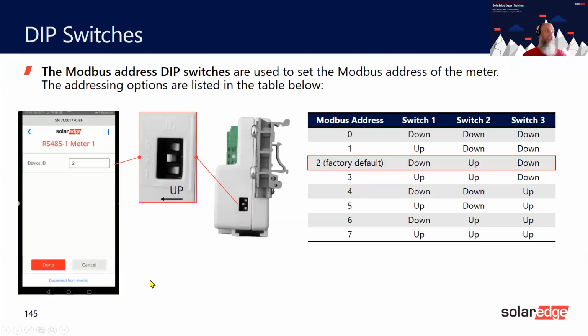Now, I did say there were dip switches on the side. This is important. What we didn't look at in the setup menu, but we will cover here, is how to address the meter with the correct ID. So you can see on here we've got ID, this bit here, we've got 1, 2, and 3, and 1 and 3 are down, but 2 is up. And that relates to the information that you would put in on the setup for the meter ID as 2. So this is saying I'm number 2, and then you need to put number 2 in, or this one won't connect.